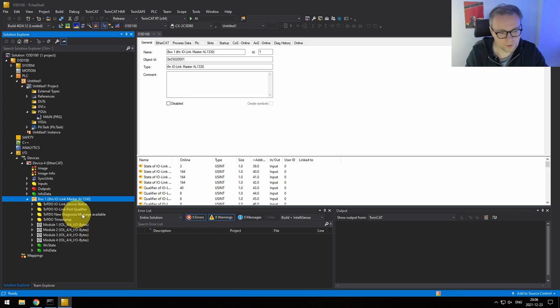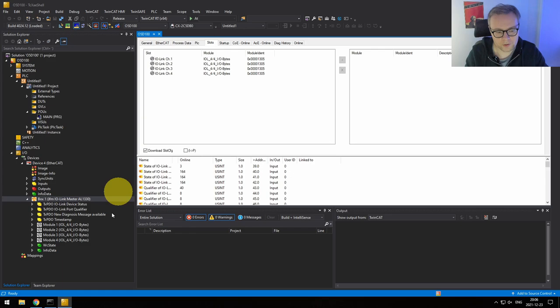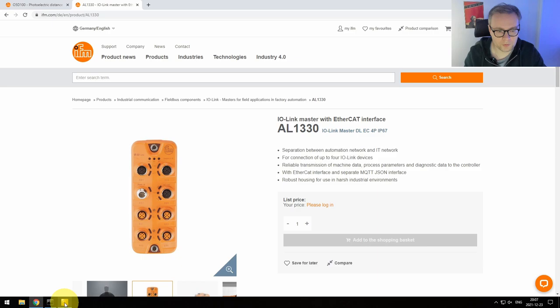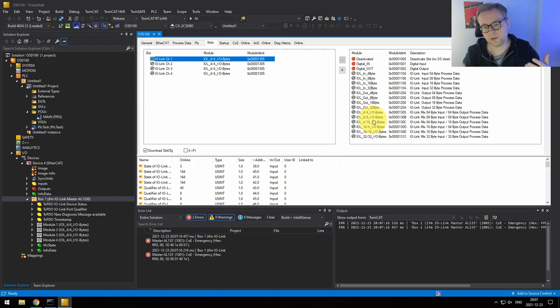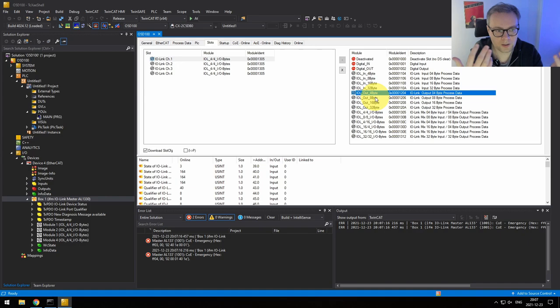Looking at the IFM AL1330, it has 4 different channels, so we can connect 4 different sensors or actuators. There are other variants with 8 or even 16 ports. For the first channel, we need to define how many bytes of process data are going in and out. Every IO-Link slave has a predefined set of process data — it can be 1 byte, 2 bytes, 4 bytes, or up to 32 bytes per sensor. To find out what our sensor handles, I open the documentation for the IFM O5D100 distance sensor.